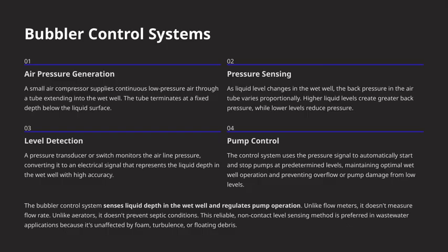Next, the pressure sensing part comes into play. As the liquid level in the wet well changes, it affects the back pressure in the air tube. When the water level rises, it creates greater back pressure, and when it drops, the pressure decreases proportionally. This variation in pressure is then monitored by a pressure transducer or switch, which converts the pressure into an electrical signal. This signal accurately indicates the liquid depth in the wet well.